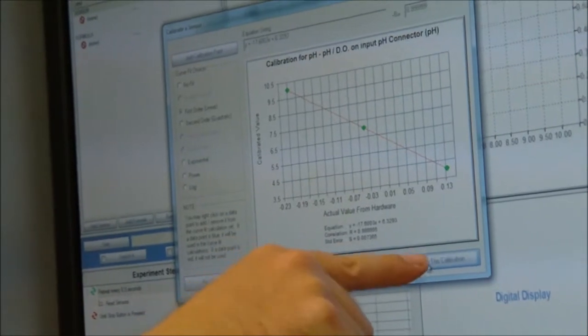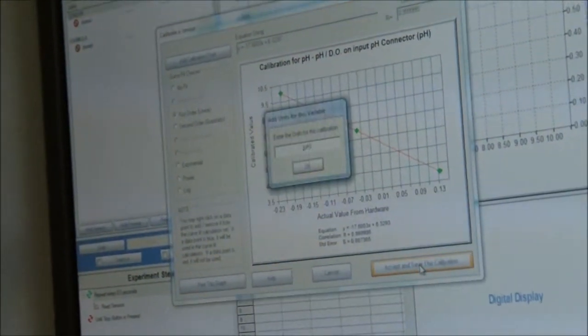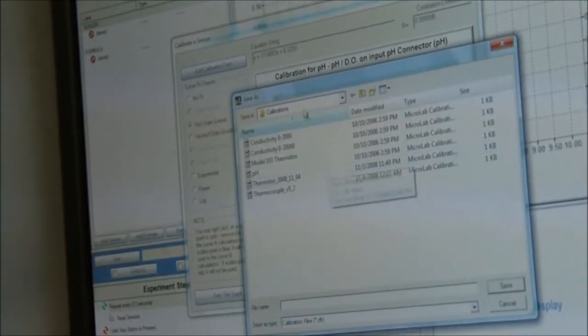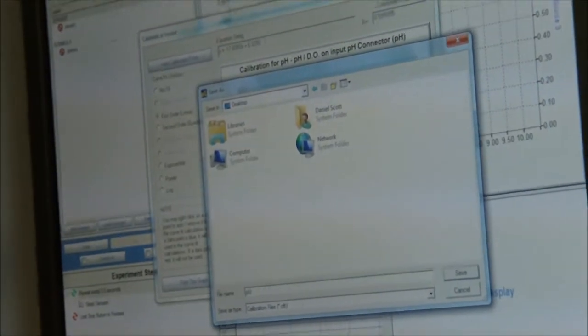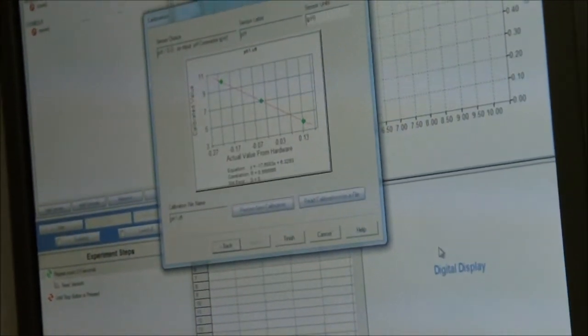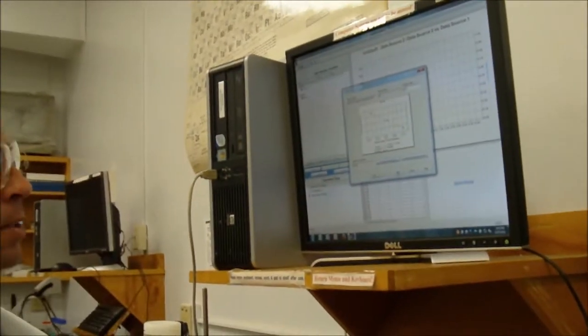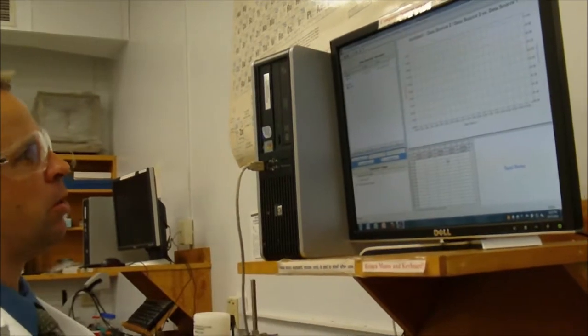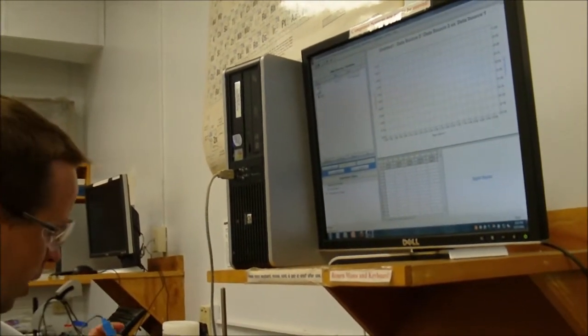And then I say accept and save this calibration. And it's going to ask me what I want my units to be, and pH is fine. I'm going to save my calibration on the desktop, and I'm going to call it pH1. That way if my microlab gets disconnected somehow, I can go back to that and the calibration will be faster the next time. So I click finish. Now I have a pH probe ready to go.